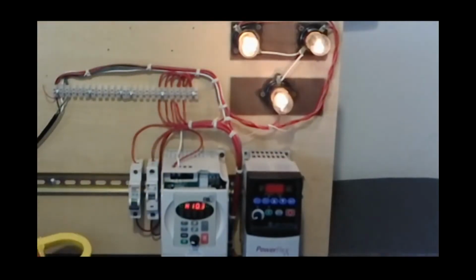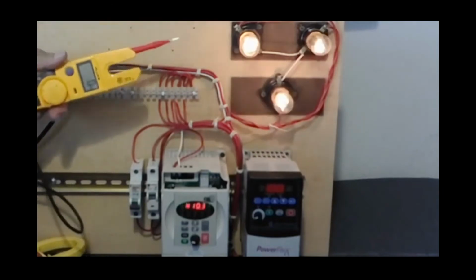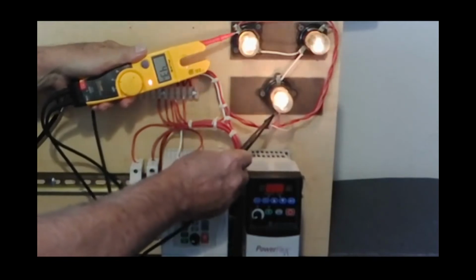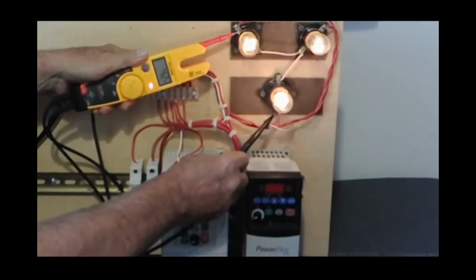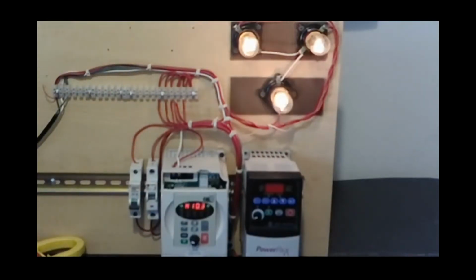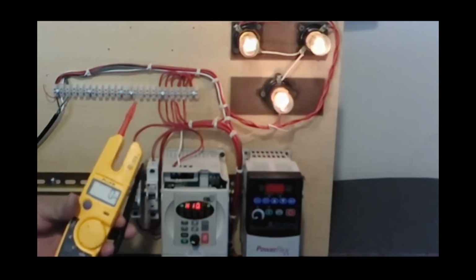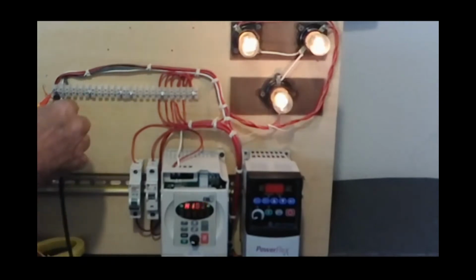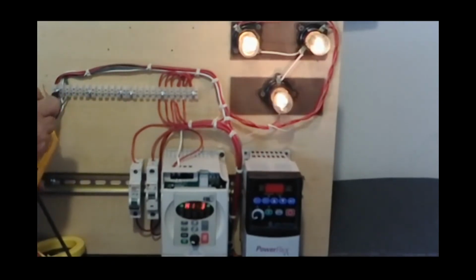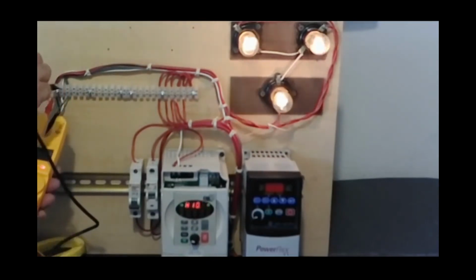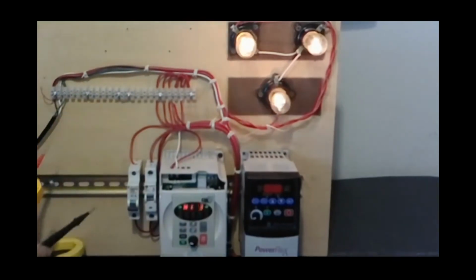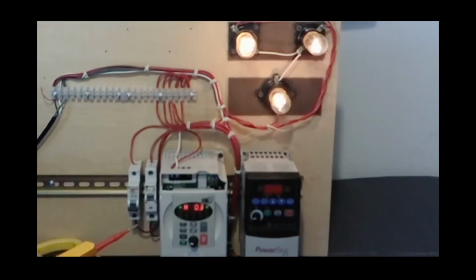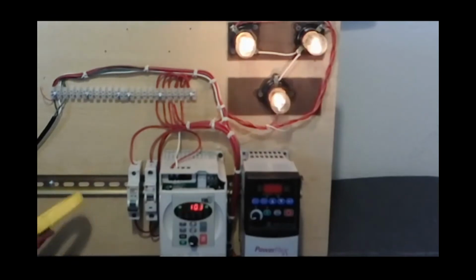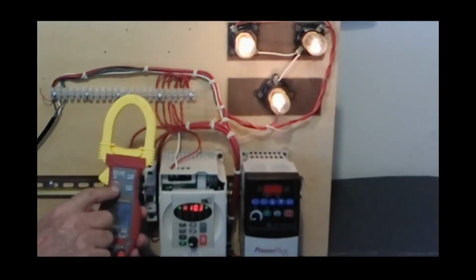But now, not all meters are going to read that drive. If I take a standard meter you probably use today, and I measure the same load right there, what I'm seeing on the meter is 43 volts. There's a big difference in voltage. That's because of the difference in the sine waves. The average responding meter can only read the average response of the sine wave coming in. So if I were to measure power coming in, I'm going to get exactly what I need at 120 volts. Kind of hard to see at this angle, but I've got 121 volts coming in. But now, going through the drive, the sine wave changes to pulse width modulation. So the only type of meter that will read the output of the drive has got to be identified as true RMS.